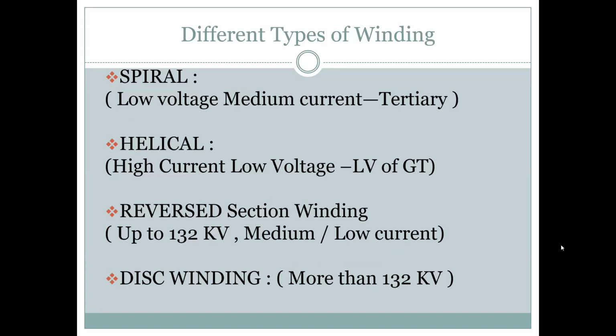Next. Windings are different for different purposes of use. Spiral, low voltage, medium current, and tertiary. There are three winding transformers also. The tertiary winding, they call it. So normally spiral winding is used. Spiral is the most simple winding.